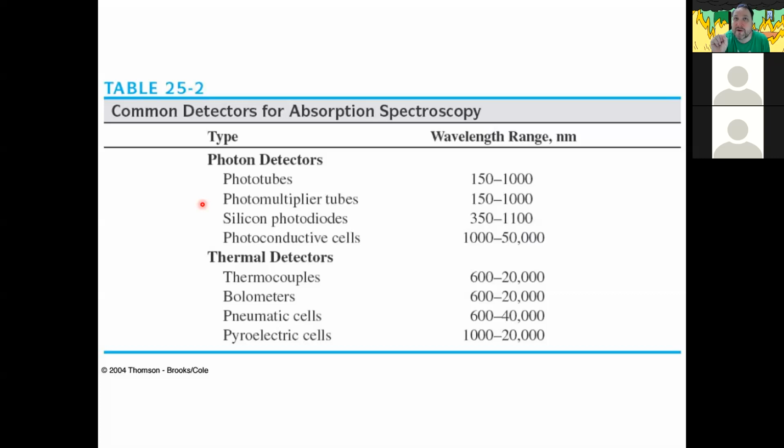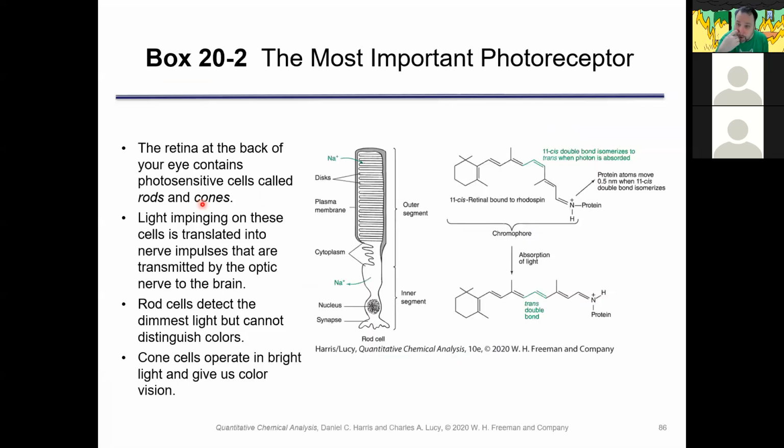There is a very slow process of change by which people who do separations adopt new spectroscopic instrumentation. So I think the detector on our HPLC is a diode array detector, a DAD. It's a DAD, got the DAD bod. So the diode array detector is pretty much the only other place you're going to see a silicon photodiode. In places where those have been, they've been largely replaced with CCD detectors, so basically camera chips instead.